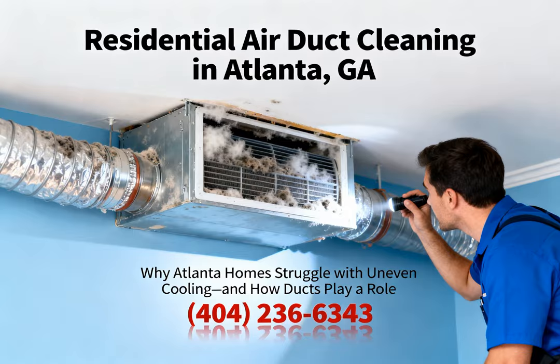Exactly. Think of it as taking the blood pressure of your home's respiratory system. They use specialized gauges to measure the exact resistance the blower motor is facing. Making sure it can handle the blanket. Right. They need to ensure the motor actually has the horsepower to pull air through that dense wool blanket of a filter without straining. What happens if they don't test it and it is too much?